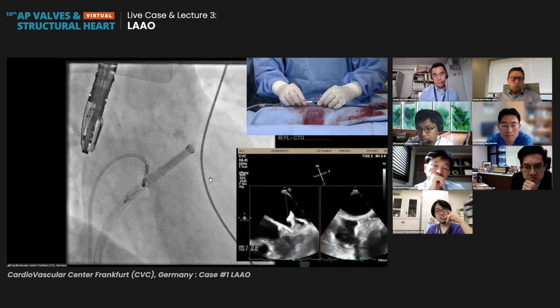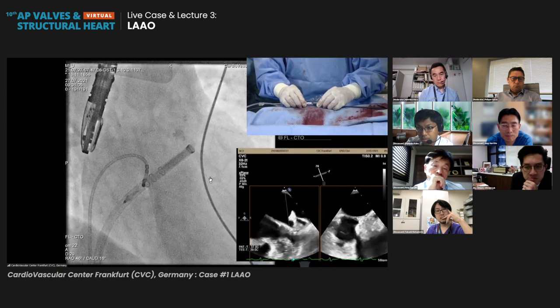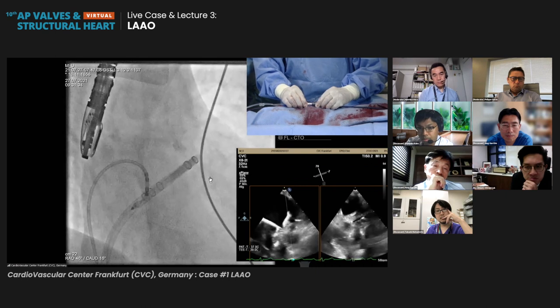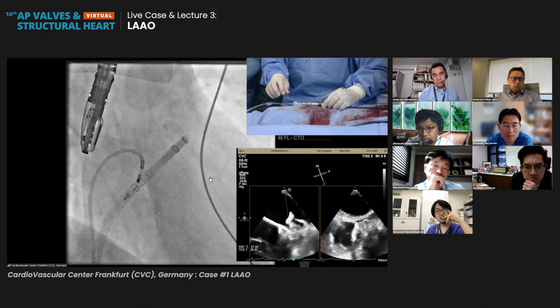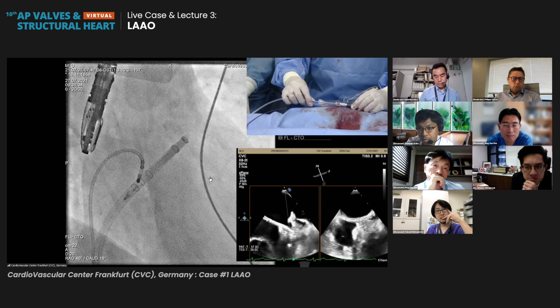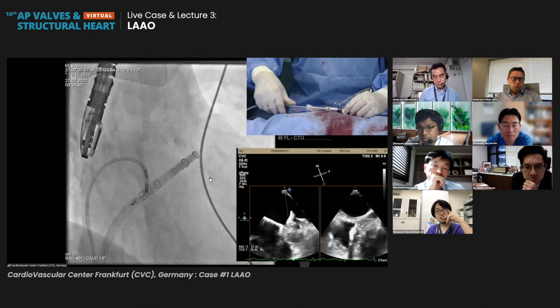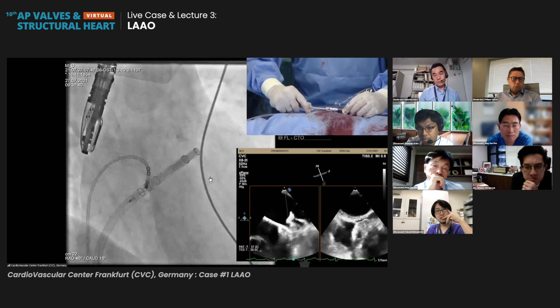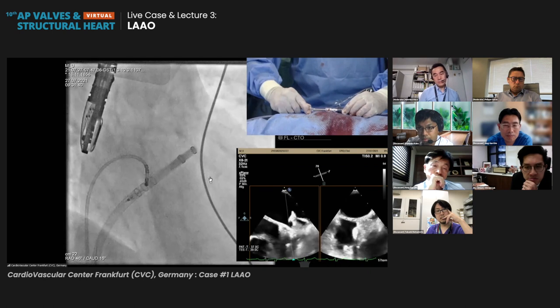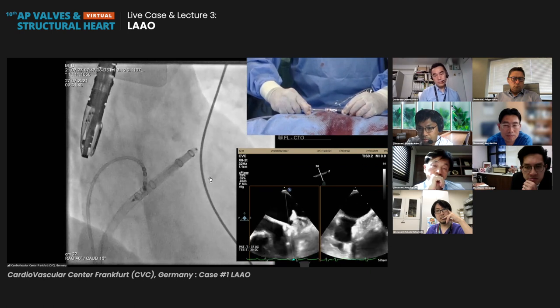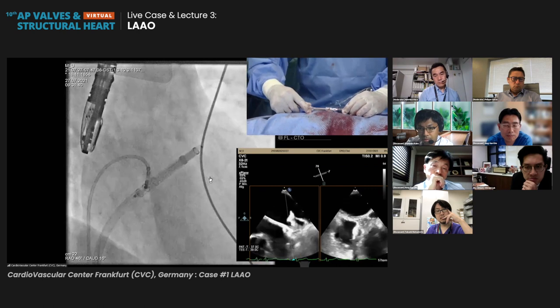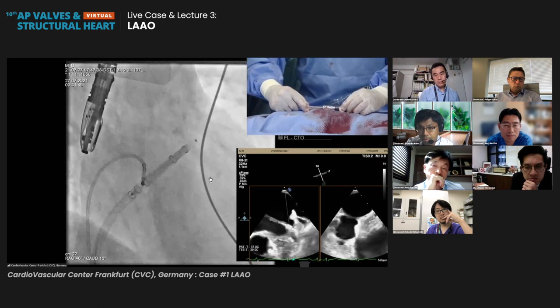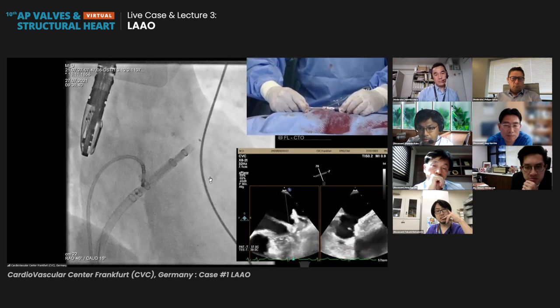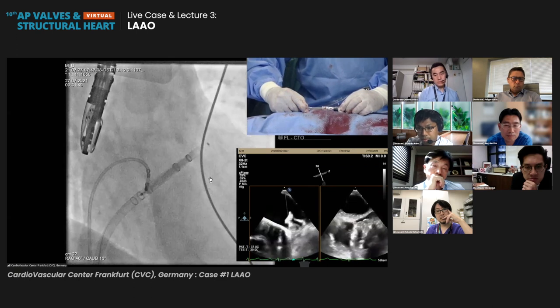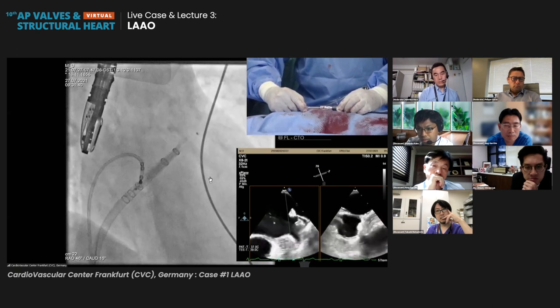I'm connecting now the delivery system. That's like with the old Watchman. I'm connecting the delivery system with the sheath. And now I start opening the device. Now you see the distal marker. And I open it so far that the diameter of the device is twice the diameter of the sheath.